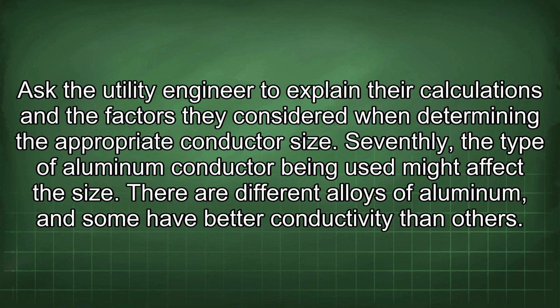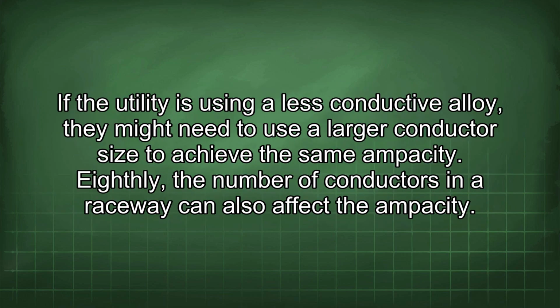Seventhly, the type of aluminum conductor being used might affect the size. There are different alloys of aluminum, and some have better conductivity than others. If the utility is using a less conductive alloy, they might need to use a larger conductor size to achieve the same ampacity. Eighthly, the number of conductors in a raceway can also affect the ampacity.